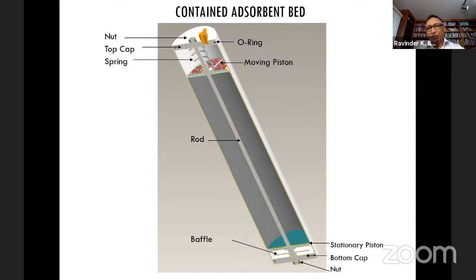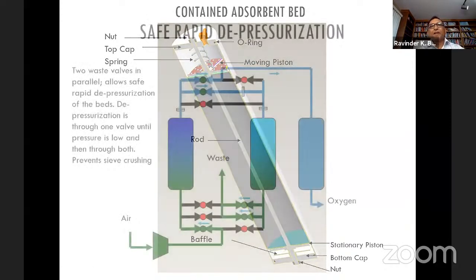So when you start to pressurize and depressurize, every time it moves up, moves down, it's like somebody is banging on it all the time. And there is always some settling in the bed. So unless and until you have a moving piston, the sieve will powder. So the bed design can be different for concentrators.